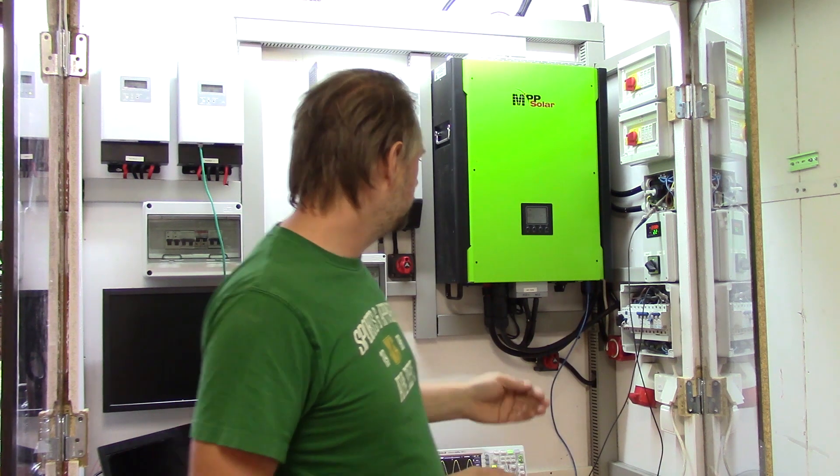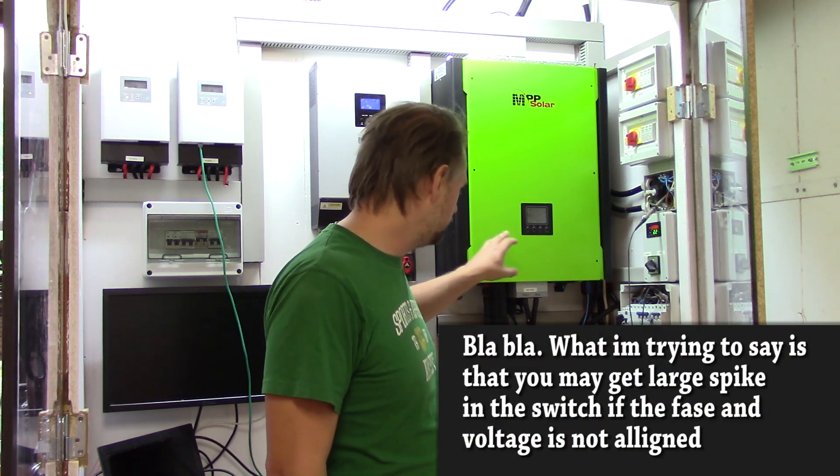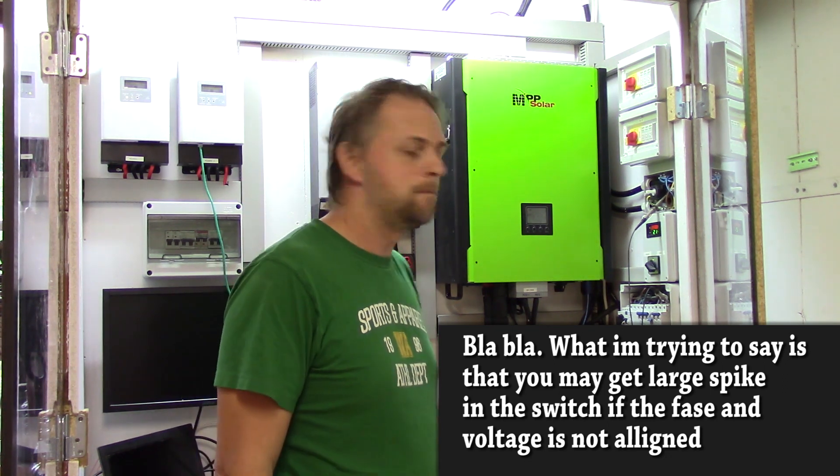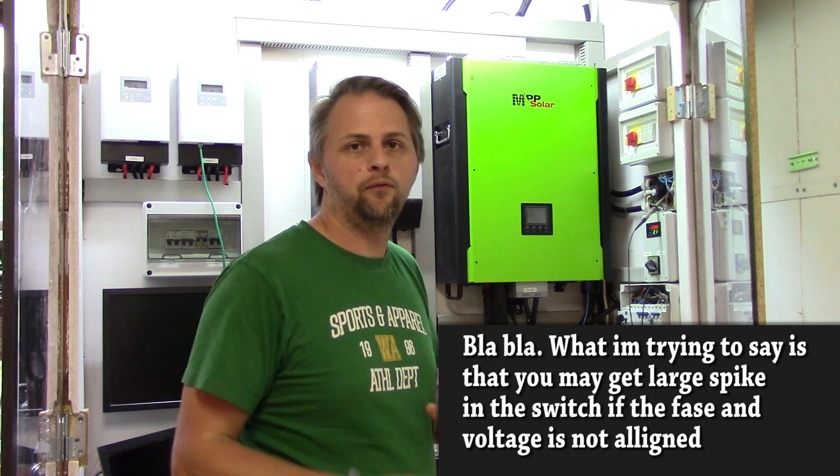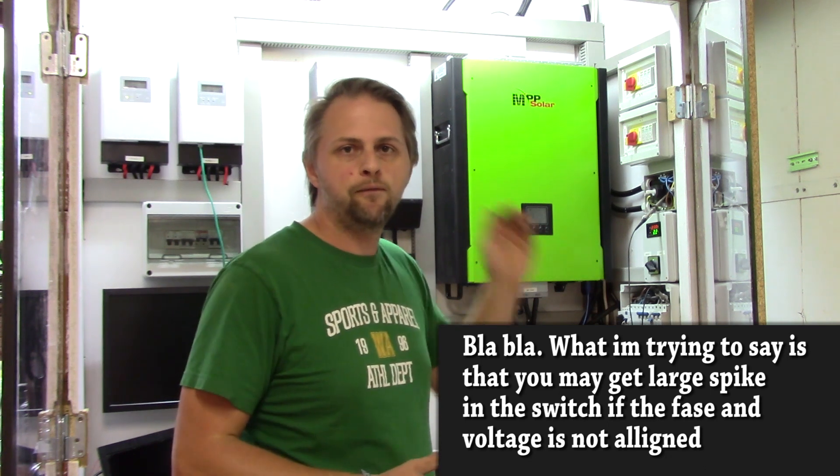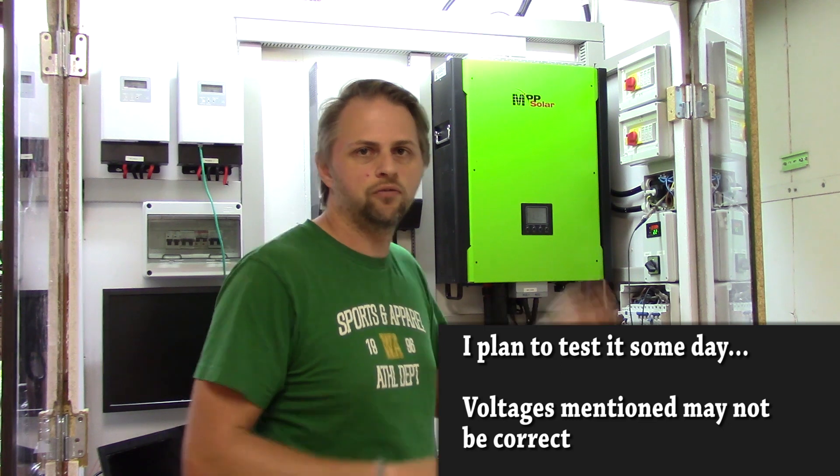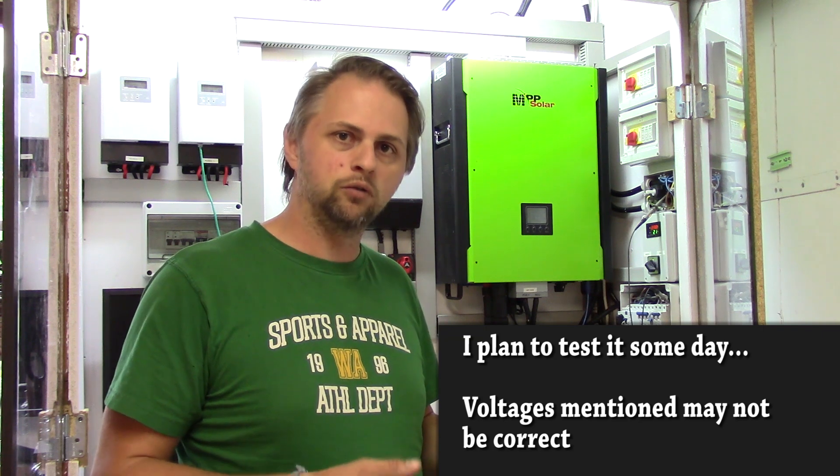There is one thing that I know I have mentioned a couple of times: imagine that the inverter does not synchronize with the grid. What could potentially happen is that you go between minus 110 volts in my case to plus 110 volts. If you are looking between phases, you may go between minus 300 and plus 300, and then you break equipment. And that's when you actually need it to be very important with inverter synchronization with the grid.